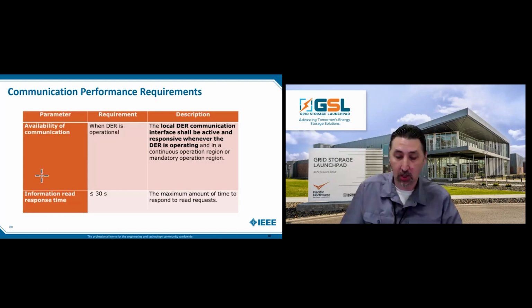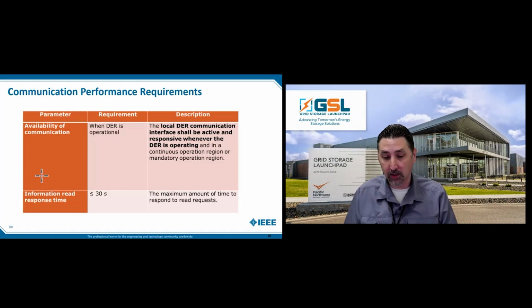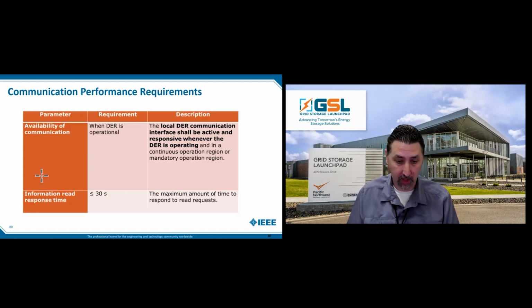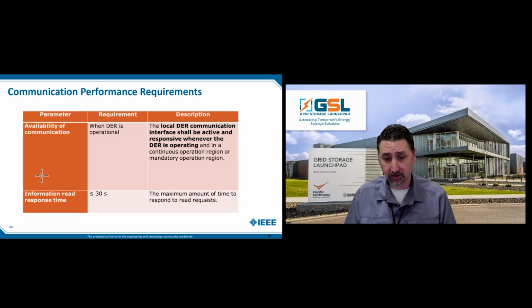We're also talking about this in the context of EVs. Technically, in order to be a DER, the EV and EV charging station both need to be co-located together. If there's no EV plugged in, is the DER operating? I need to be ready for the next DER, so maybe I need to be available to change my settings before the EVs arrive and start doing their V2G thing, if that occurs. The current 2018 version says it must be active and responsive whenever the DER is operating, but this is one of those areas where you should confirm, when the new revision is complete in another year and a half or so, that it's still the case, because the DER's local communication interface may always be supposed to be available.